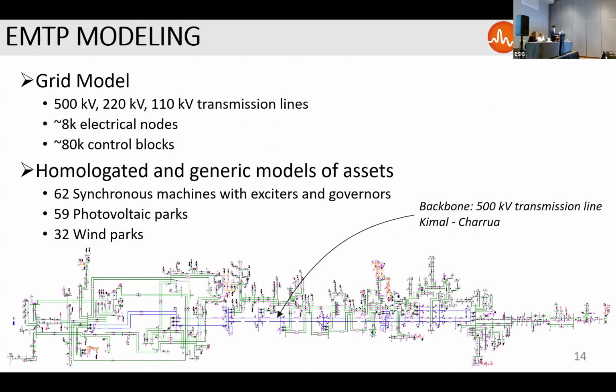So we modeled, well, actually the Chilean company CEN modeled the transmission grid at 500, 220, and 110 kilovolt level in EMTP with roughly 8,000 nodes, many control blocks, and many models of renewable generation. Some of them were homologated with manufacturer data. Some of them were generic because of sometimes lack of data, sometimes lack of time. And the backbone of the Chilean transmission system, as we mentioned at the beginning, is the 500 kV transmission line that goes from the north to roughly the center-south region.